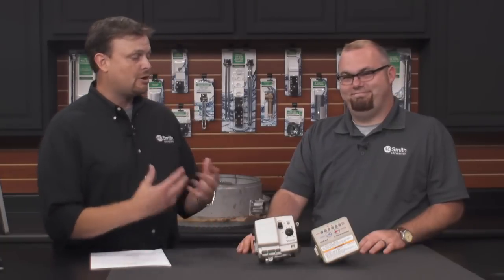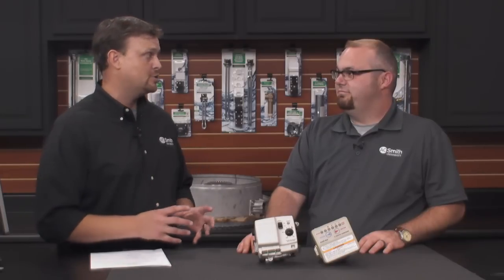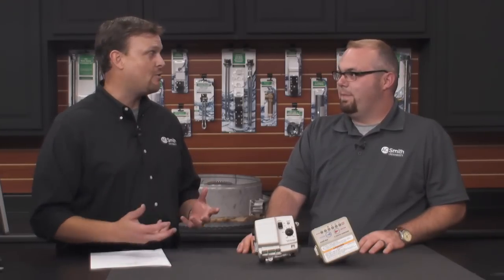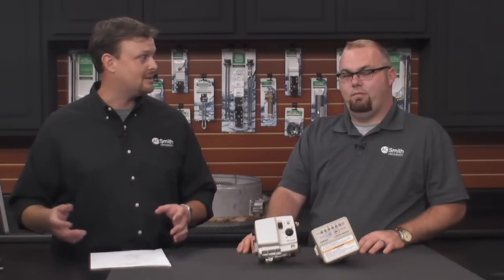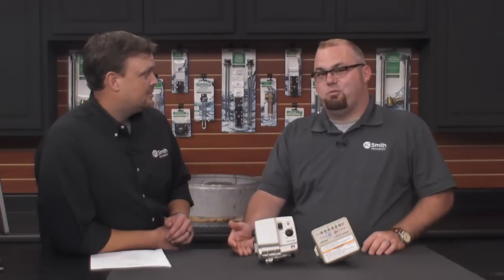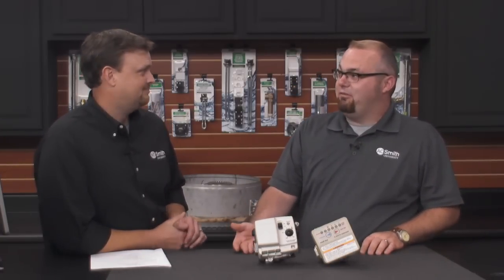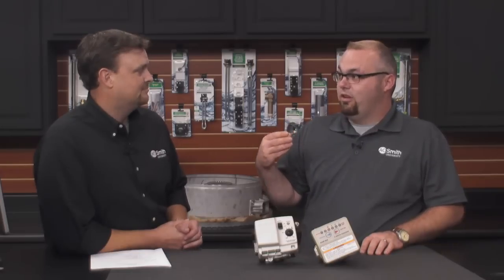First off, when we're talking about power vent water heaters, we make many different styles of water heaters. Why would somebody want to go with a power vent water heater as opposed to, say, a standard atmospheric or another type of water heater? Well, usually the power vent offers more venting versatility. An atmospheric vent water heater has to vent through the roof, using typically expensive B vent, which is kind of high price, right? But with the power vent, you can get away with using PVC. The distances you can go are a lot further, plus you can vent it from a sidewall or out of the roof. Oh, that's a lot better.